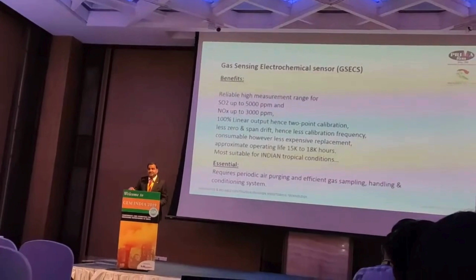Second part, somebody says that my emission levels are only 200 ppm, why should I go for 5,000? You can go for 1,000 ppm with the same sensor. So the flexibility is given here. The NOx we can go up to 3,000, again the same facility, flexibility is provided. As I mentioned, 100% linear, with less zero and span drift, hence you can avoid the calibration that normally in other technology you have to do, with daily drift or zero testing. You have to do it automatically daily. Here you can avoid that.